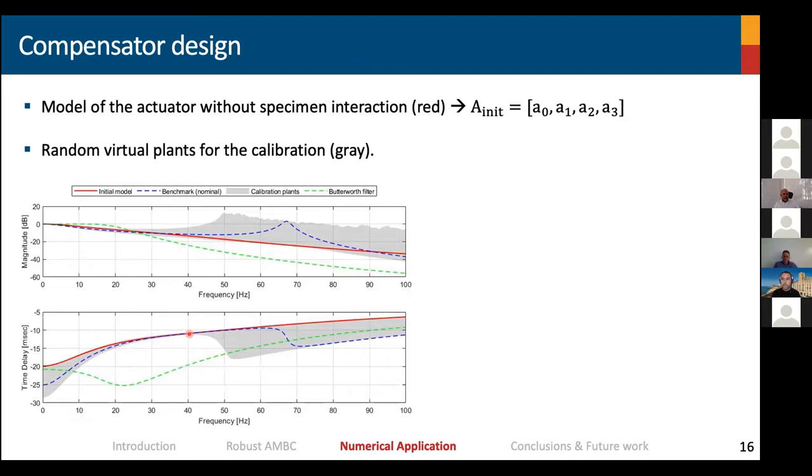The model of the actuator without specimen interaction, we consider those values to design our adaptive parameters A, which I call A initial. And this is the initial values of the adaptive parameters, not the adaptive gains. In this figure, I can show you in red, the initial model. Basically, this is the actuator, bare actuator without specimen connected. And the blue curve is the actuator with specimen interaction. You can see that there are some significant differences between the red and blue curve when we connect a specimen, especially in the time delays. In gray, I illustrate different virtual plants that were considered through uncertain parameters.